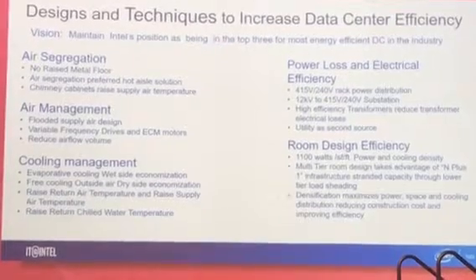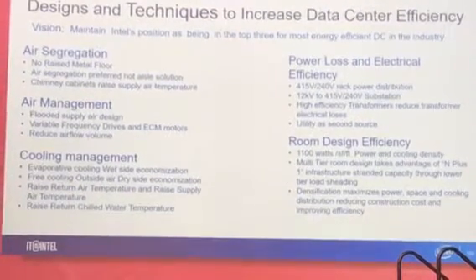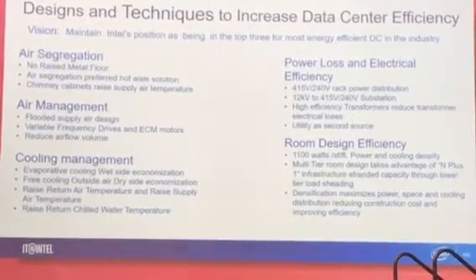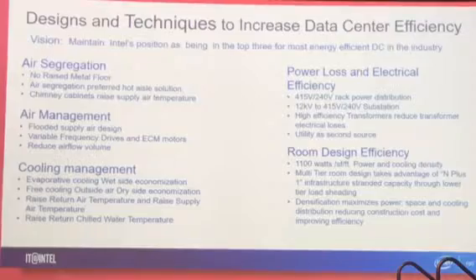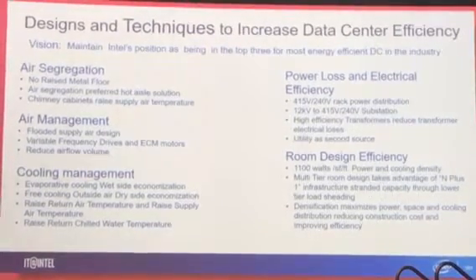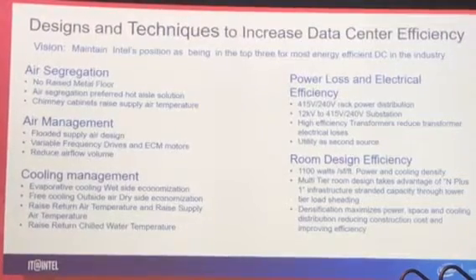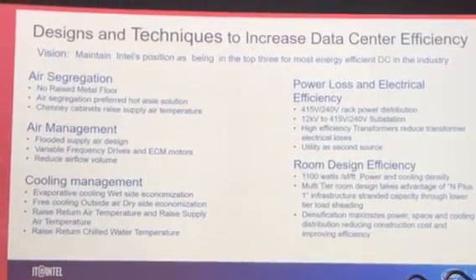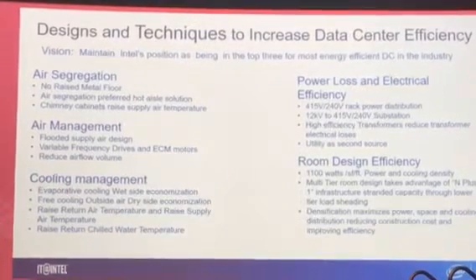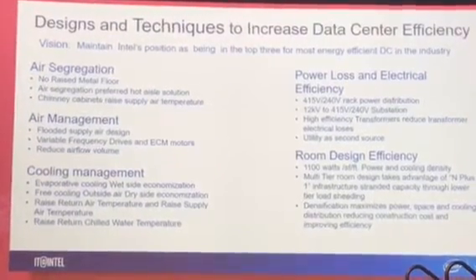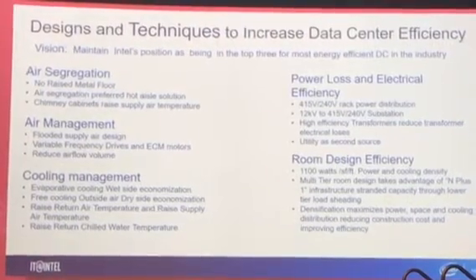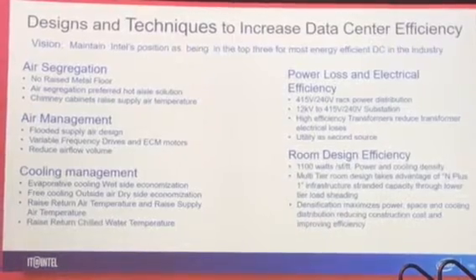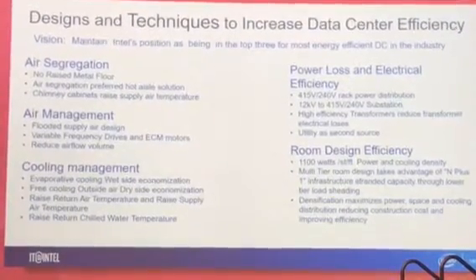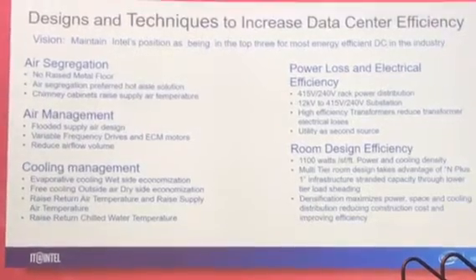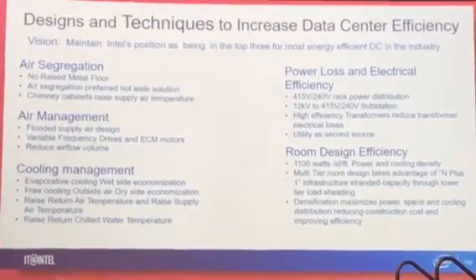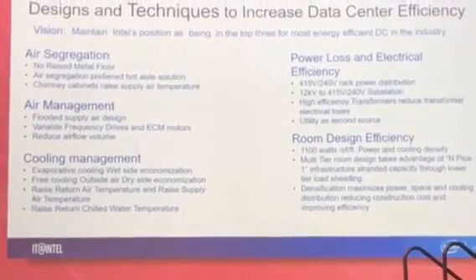We went to a 415, 240. One important thing that we did with feeding the servers, we have 3 phases. The utility power data from the company shows that most of the sags are happening in one phase, and the other 2 still remain balanced or stable. So if you feed the server between those 3 feeders, phase A, phase B, and phase C, even if one fails, the others might keep the servers running. And actually, after 3 years or 5 years, we don't have many issues with power disturbances.